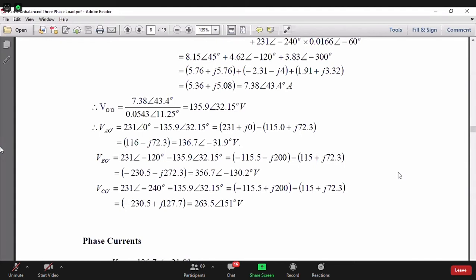If you have a tube light in A phase, it will not glow because the voltage is 136 volt. And if you are unfortunately in the B phase, all your sophisticated equipment will simply burn. Their power supply unit will simply burn. Your very good TV, you will see that white smoke is coming out.